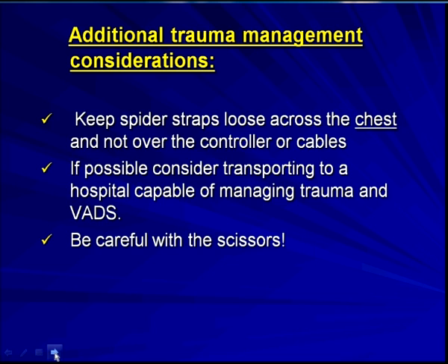I know we've had cases here in the Mid-Atlantic region where cables were cut accidentally, and if patients are critical, some people do tend to get a little loosey-goosey with the scissors. We don't want to cut something that's basically going to seal the fate of the patient. So if you do palpate something underneath the clothing that shouldn't normally be there, like a controller or batteries, make sure you expose the patient first before you start cutting around these key elements, because once we cut any cable that may be the driveline, we seal their fate. Next slide.